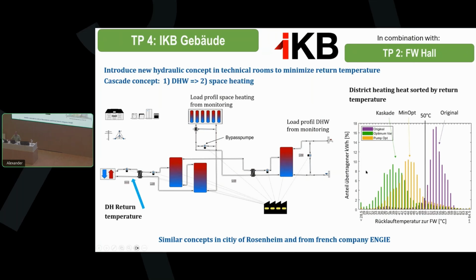As you can see in this diagram on the right side, the violet is the original measured system. You see on the x-axis the return temperatures weighted by the energy transported. So we can see mainly around 54 degrees. We transport here a maximum of 17% of the heat over the year. You see, beyond the right of 50 degrees, it's more or less all of the heat transfer. So quite often we have very simple optimization possibilities, just pumps with much too high flow rates as a standard setting.